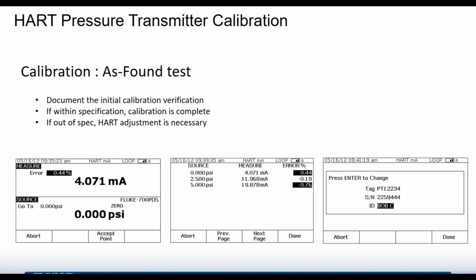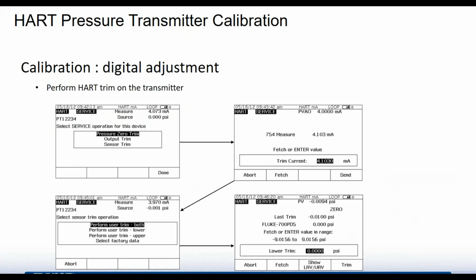Once those calibration points are taken, since you're using a documenting calibrator, you've got your tag ID name and your serial number, which are automatically put in because HART has captured that information off the transmitter. Put in the name of the person that's doing the calibration, and you've completed the as found. So at this point, if everything was in spec, then you've finished your calibration and you go on to your next transmitter. But if it's out of spec, now you're going to have to do some adjustments.